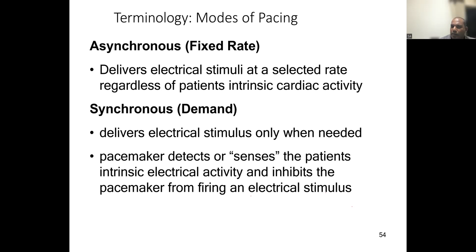So remember I mentioned the concept of sensing. When a pacemaker is capable of sensing what's happening inside the heart, that's the on-demand mode. There the patient's pacemaker can wait and only pace when there's actually significant bradyarrhythmia. It can change what it's doing from beat to beat even. So it might pace on a certain beat, and then a few milliseconds later it might not pace, because the patient gets a reasonable cardiac activation. In asynchronous pacing, we keep the sensing option off, so the pacemaker can only deliver current output on a given time scale or at a given rate.